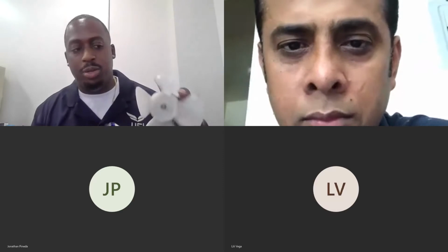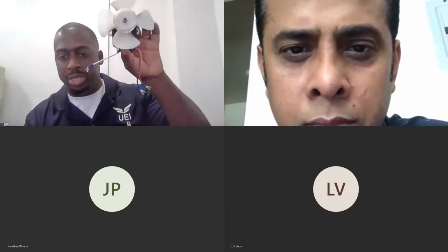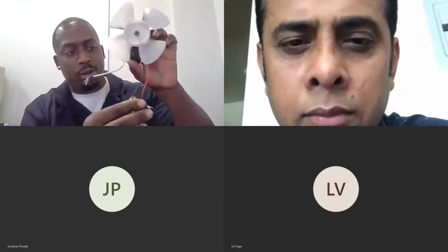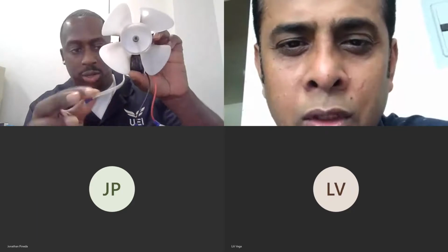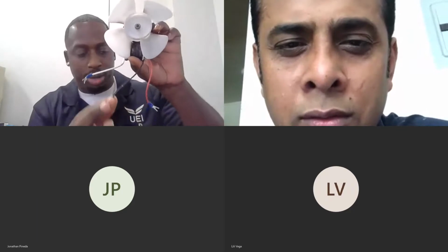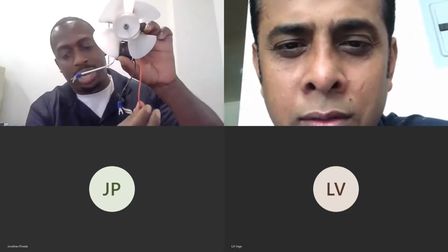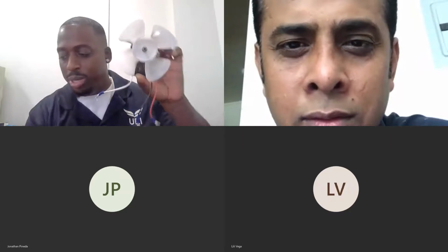So one of the fans that we used last week was this one. This is our two-speed fan. Notice that it has three wires. It has the neutral wire, and then it has a black wire, which is our high speed, and then it has a red wire, which is our low speed.